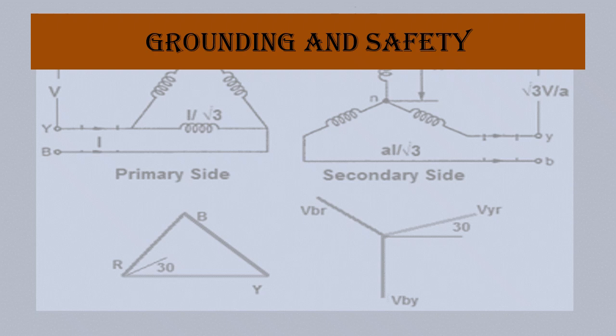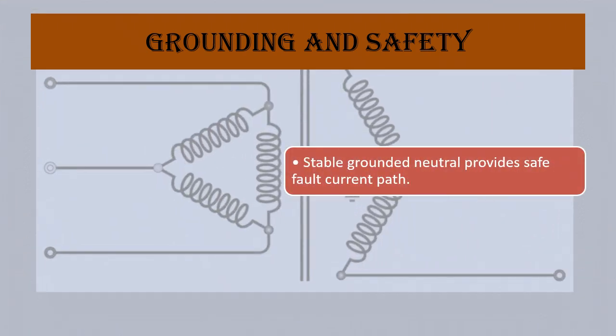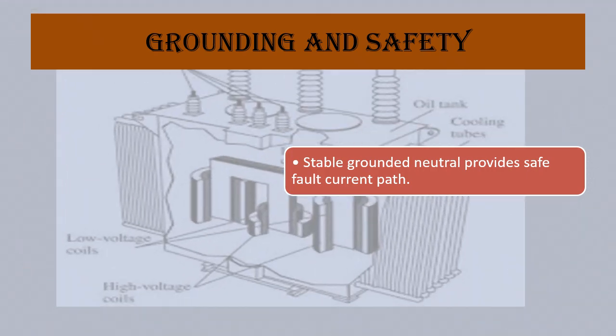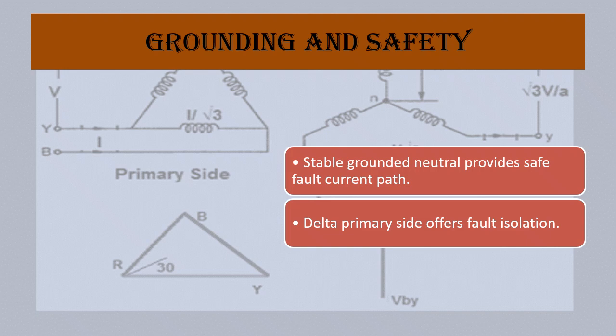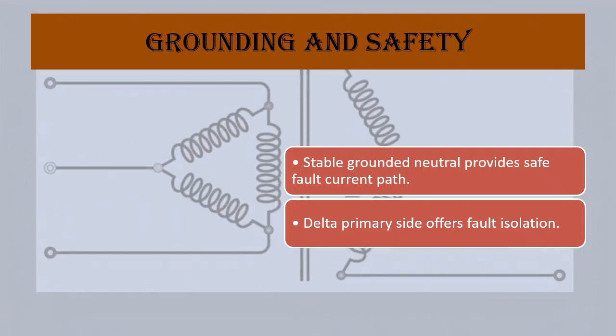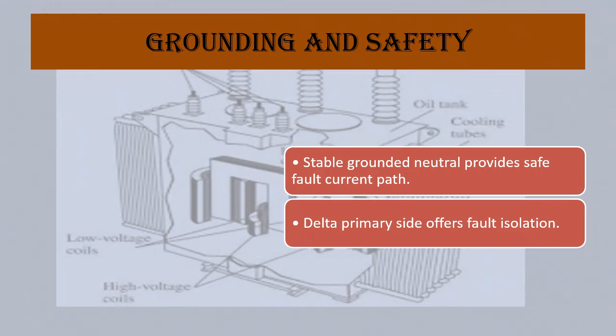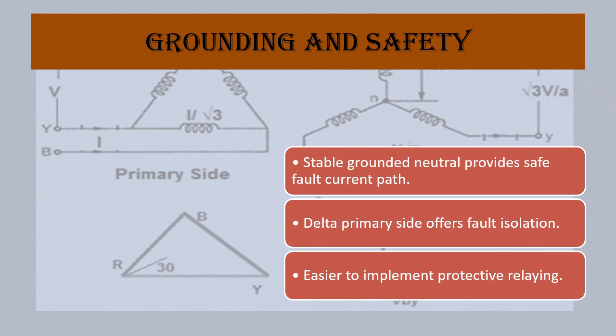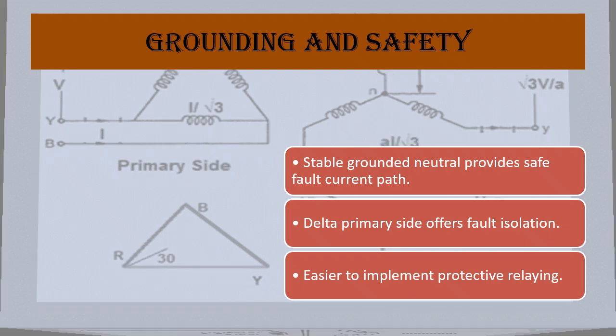Grounding and safety. The grounded neutral point on the star-connected secondary ensures a safe path for fault currents. This enhances protection against shocks and electrical fires. At the same time, the delta connection on the high-voltage side isolates faults, preventing them from affecting the entire transmission system. This simplifies fault detection and improves overall system safety.